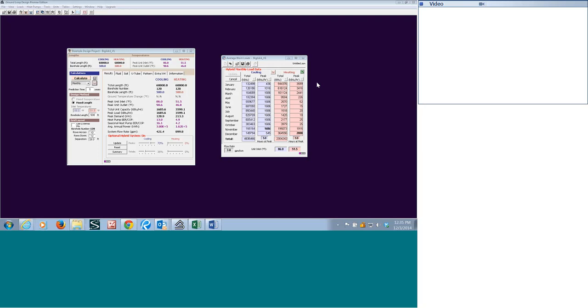What we probably would look at is the efficiency of the heat pumps, because different brands at different entering water temperatures have different EERs. So I think it would be a judgment call based on your product that's in the facility. In this case, I know the ClimateMaster TE30s, their EERs start dropping off pretty substantially above 90 degrees. The modern heat pumps, even at 90 and 95 degrees, have great EERs, but compared to at 80 degrees, it's quite a difference. So I would probably be looking at starting at 80 or 85 degrees with the auxiliary cooling device.